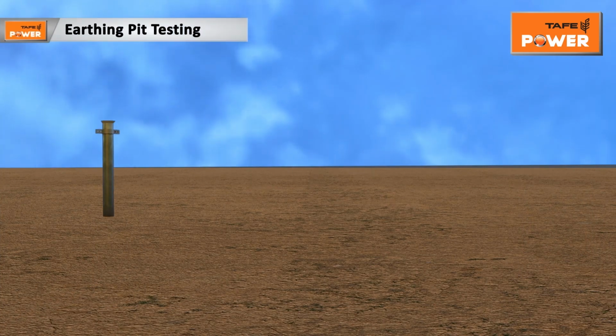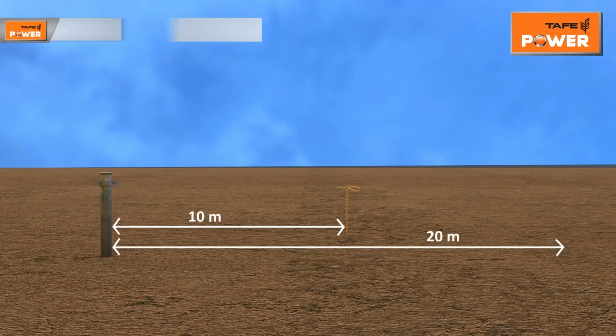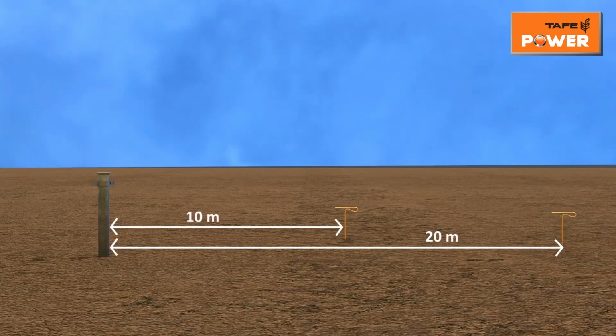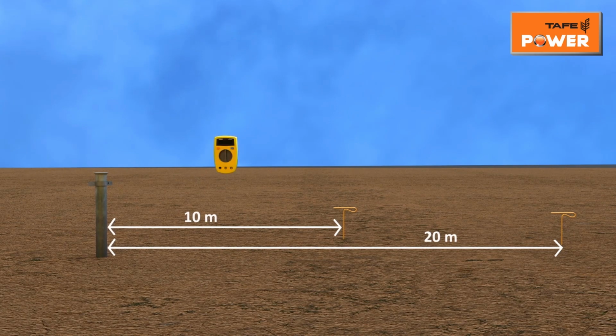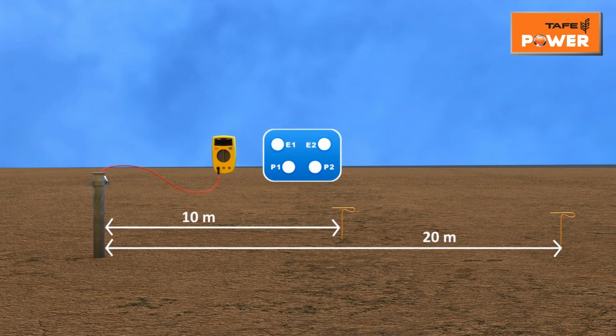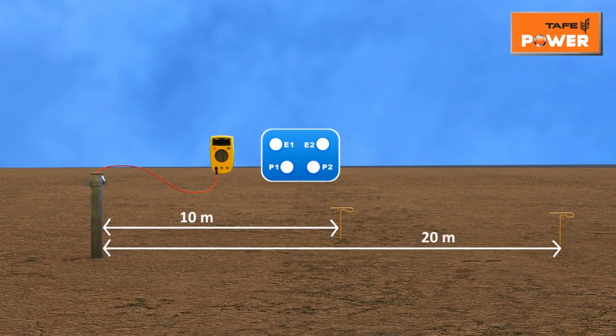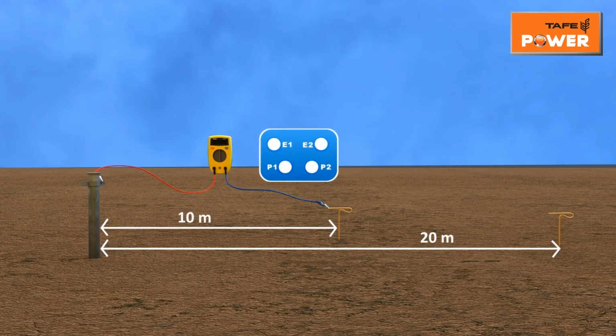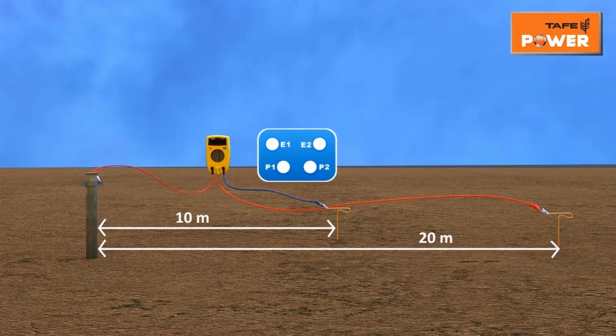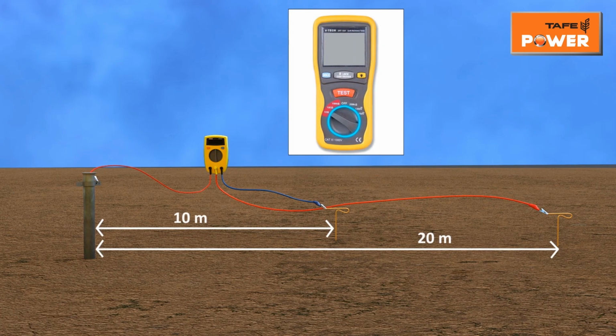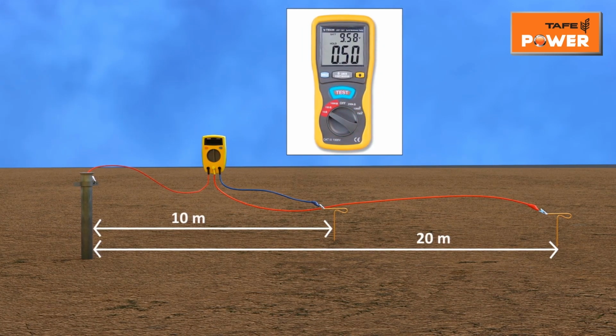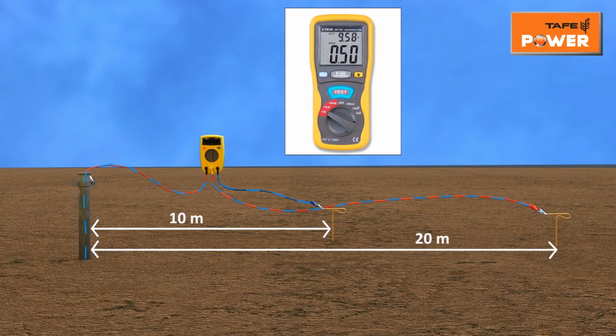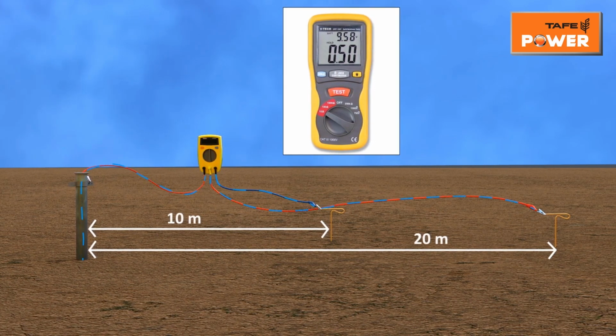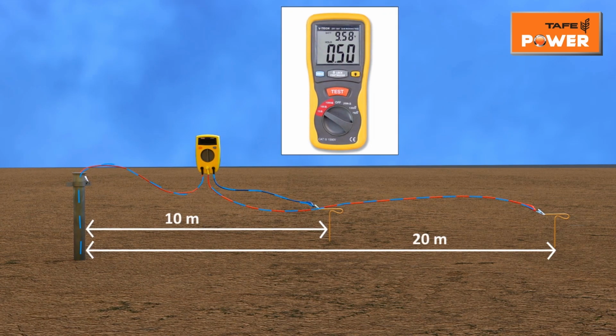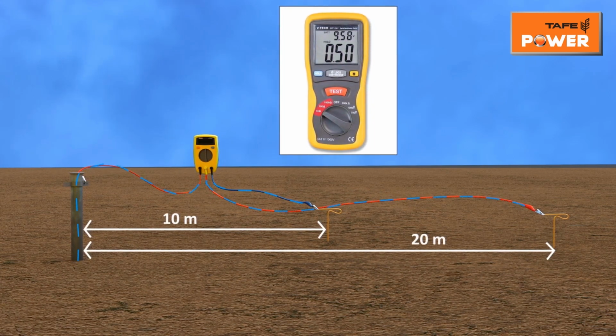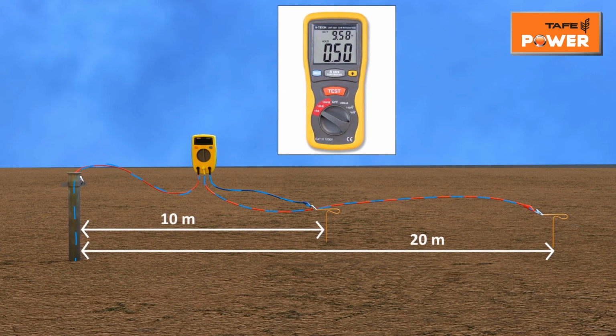Insert one test rod at 10 meters and another test rod at 20 meters away from the earth pit. Short E1 and P1 points of earth tester and connect it to earth pit. Connect first test rod placed at 10 meters to P2 and second test rod placed at 20 meters with E2 of tester. Select resistance range of 10 ohms and press test button. Ampere will flow through earth pit and test rod from meter and resistance will be displayed on screen. Resistance value should be equal to or less than 1 ohm. AC voltage value should be equal to or less than 5 volts.